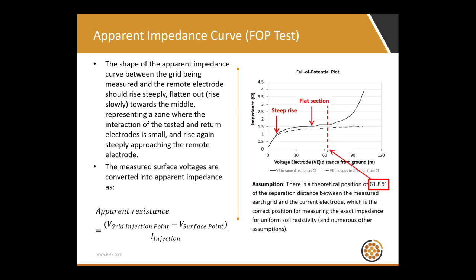There is a theoretical location, this 61.8% or 62% rule, which is the distance between the grid and the remote current injection point. The apparent impedance at 62% of that distance is recognized as the so-called exact impedance. It's a simplified rule of thumb. It is mentioned in the standards, and it's quite commonly adopted. During this presentation, we are going to investigate whether that rule is actually appropriate.